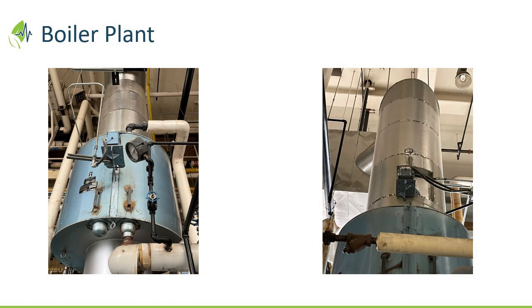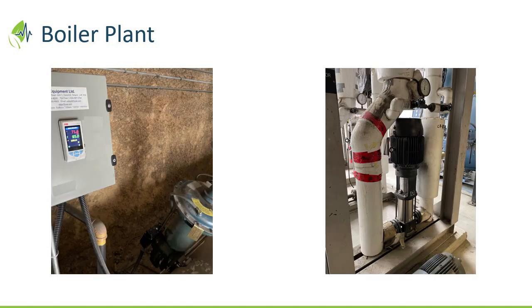And the right side picture there, above the economizer, that's the draft damper, right? Can you give us a quick summary of what the draft damper does? How should it work and what's it doing right now as far as we know? So as I noted, the old stacks are designed typically to induce a slight negative at all times. And that's because it's a lot cheaper to break draft than induce draft. So if you want to induce draft on a plant, you've got to put in an induced draft fan. You're expensive, you're running a motor, you're pulling. But if you run your stack so it's always at a slight negative, you just put a throttle on the stack to break the draft, and that's what keeps you in control. So that's basically just a damper blade in there. You can get really tight control through a multi-blade damper arrangement, but it's there just strictly to break the draft to the requirements that we want. It keeps stability across the range.